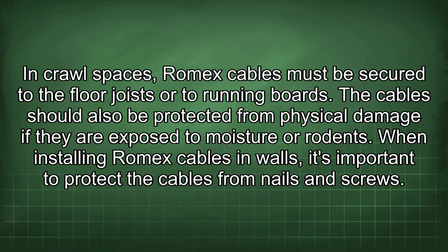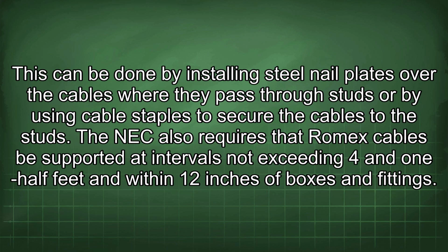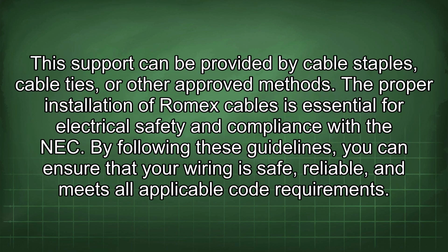When installing Romex cables in walls, it's important to protect the cables from nails and screws. This can be done by installing steel nail plates over the cables where they pass through studs or by using cable staples to secure the cables to the studs. The NEC also requires that Romex cables be supported at intervals not exceeding 4½ feet and within 12 inches of boxes and fittings. This support can be provided by cable staples, cable ties, or other approved methods.